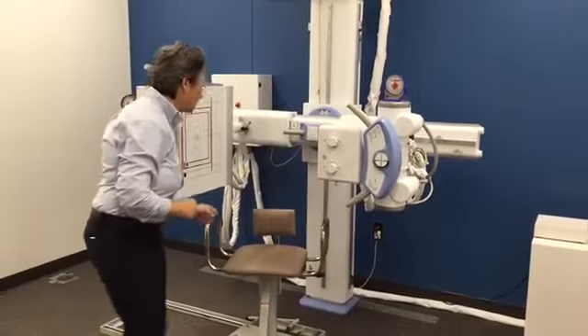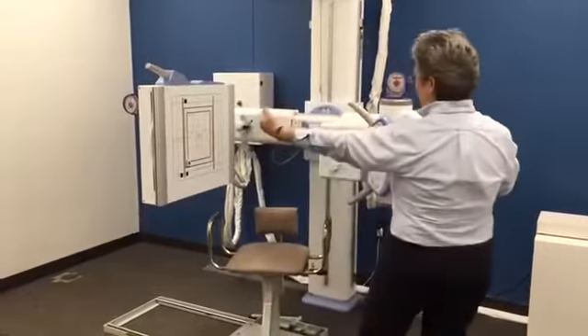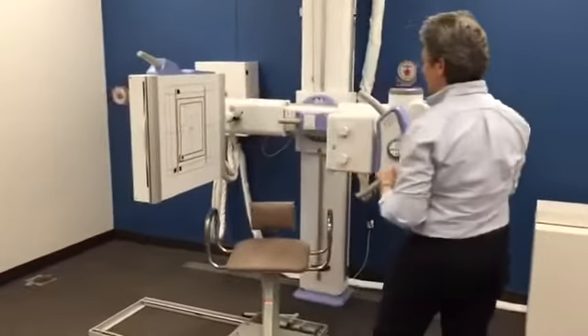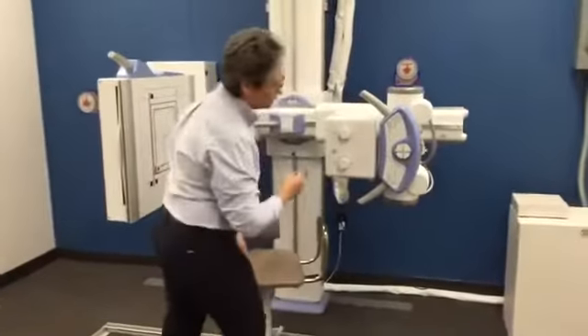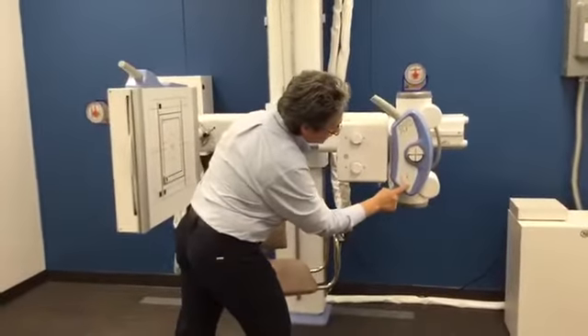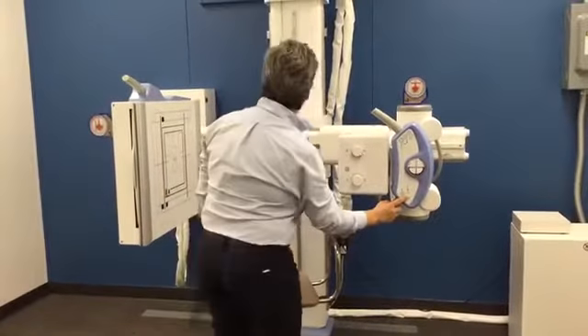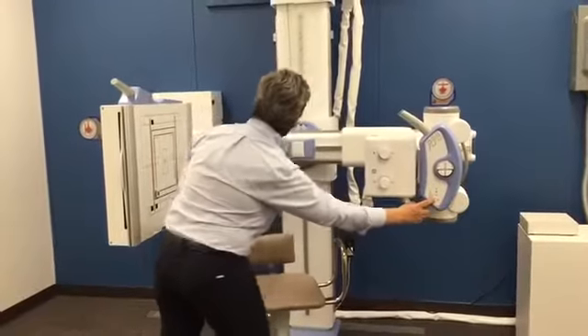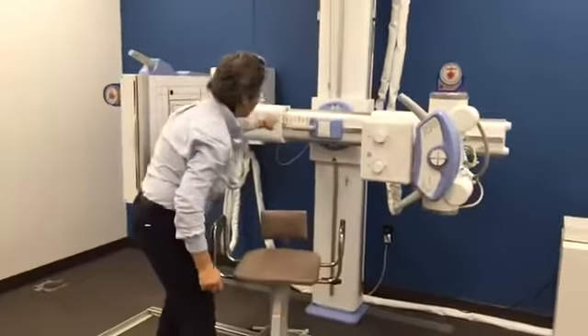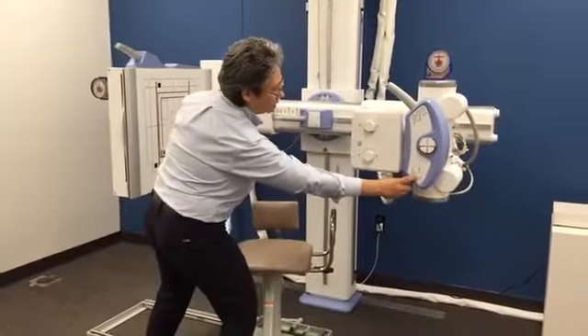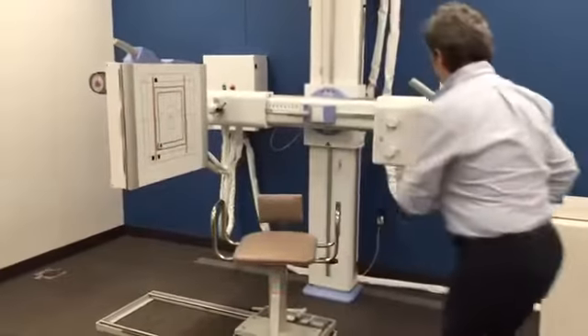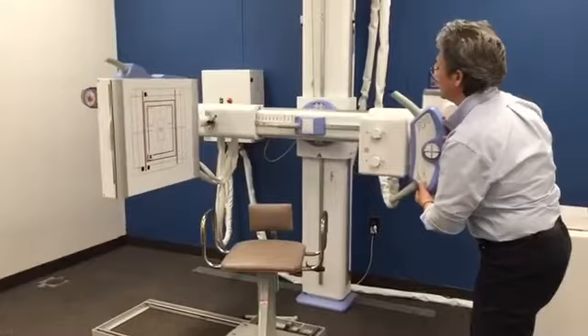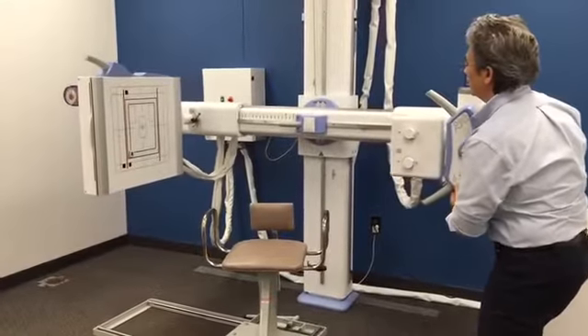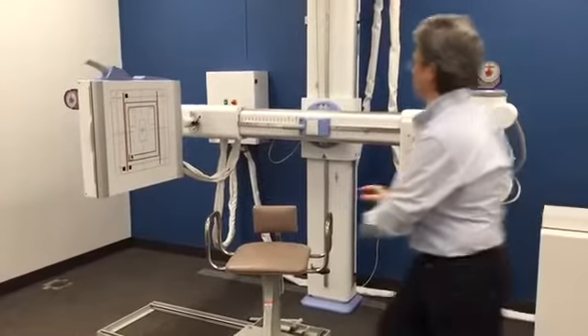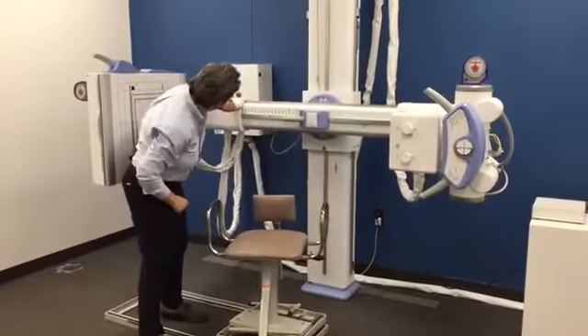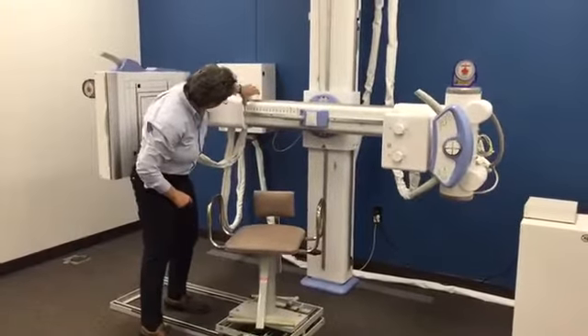So, what we need to do is increase our focal film distance. So we have to move the bucky and tube away from each other. So what we're going to do in order to move that is to use this increase SID button right here. And what you'll see as I do that is this red strip here will line up, and it will actually pause on the 72 FFD mark when we reach it. Right there. Okay? It may be hard to see, but this little tab right inside here is that 72 FFD.